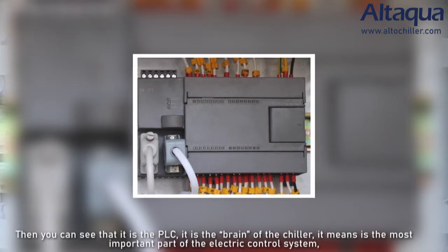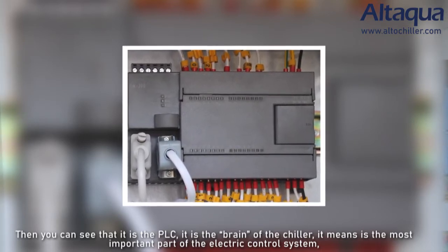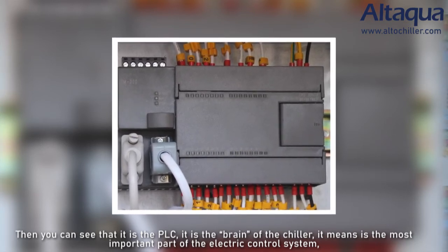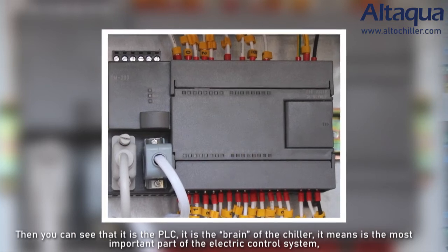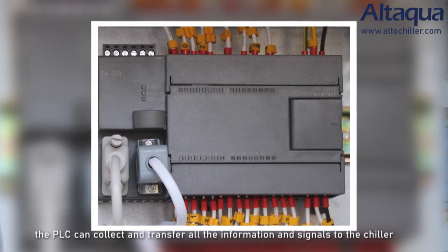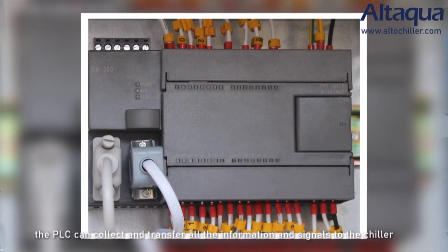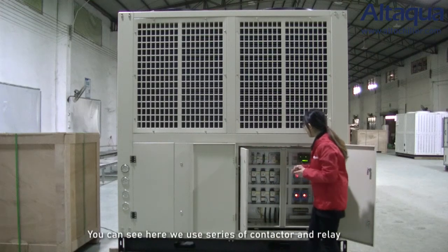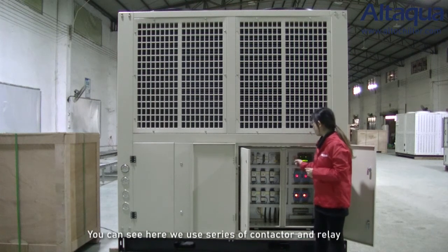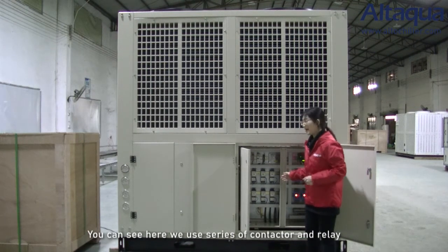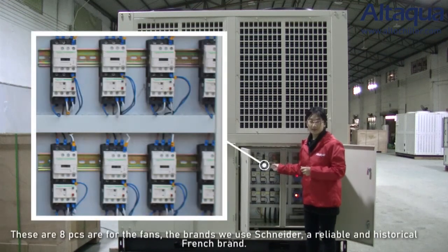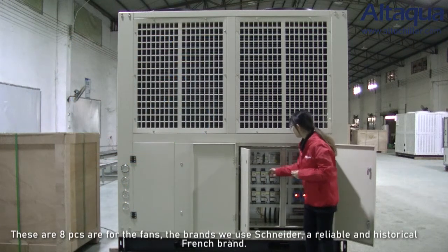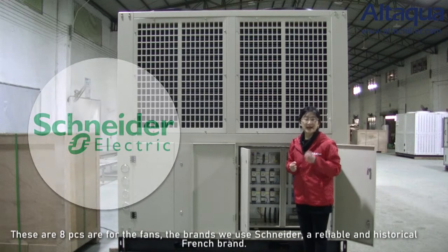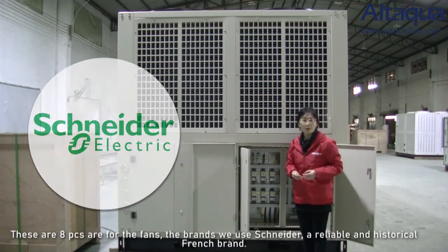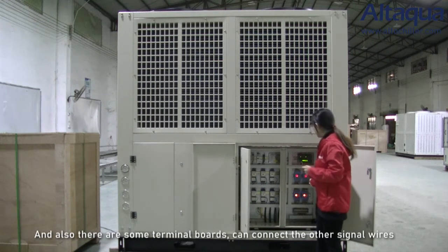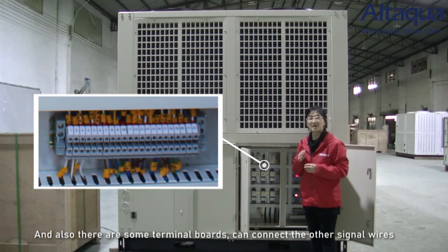And then you can see the PLC. It is the brain of the chiller. It means it is the most important part of the electric control system. The PLC can collect and transfer all the information and signals to the chiller. You can also see here we use a series of contactors and relays. These are 8 pieces. These are for the fan motors. The brand we use is Schneider. It is a very reliable and historical French brand. And also there are some terminal boards. They can connect other signal wires.